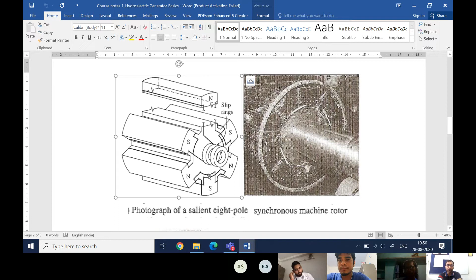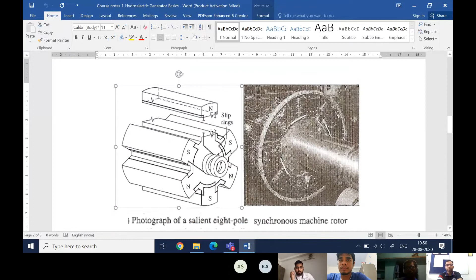But if you have this type of salient pole rotor, and we'll look briefly at the construction also, the core is still cylindrical, and on top of that you are fixing these salient poles. So this is not really a very rigid structure in terms of structural stability. If you start rotating it at a very high speed, a much higher strain or stress will be developed in these pole shoes, and it will not be sustainable for a very long duration. Maybe it can have mechanical damage very early. So that's why this can't sustain those high torques.